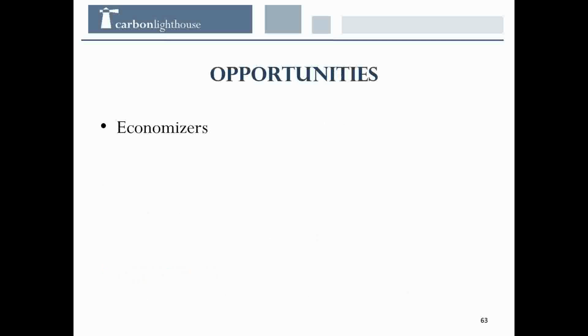Okay, so energy nerds talk about economizers a lot. There's a lot of really good studies on this. Some are done by PECI, some are done by PG&E, others are done by independent contracting firms. But basically, they all come to about the same number, which is around 2/3 of economizers in the field are broken in one way or another. So this means either the dampers are rusted and can't move, or the linkages are broken, the actuators are broken, sensors aren't working, something's broken. So that makes economizers a really good place to look. Even in the Bay Area, where there's not that much heating or cooling costs, if you have more than a 10-ton unit, it can often be worth it to check out the economizer.